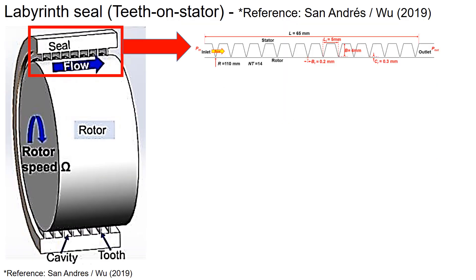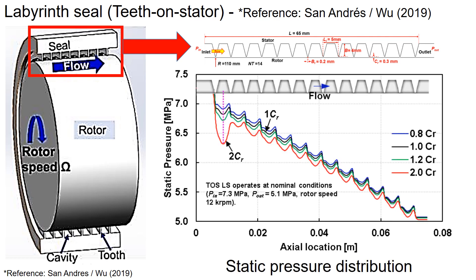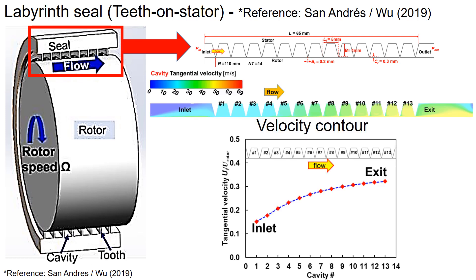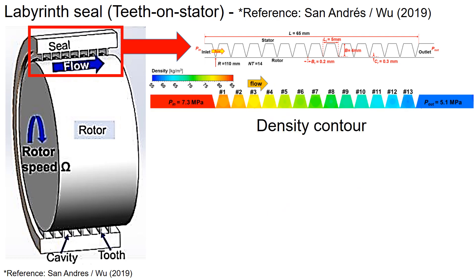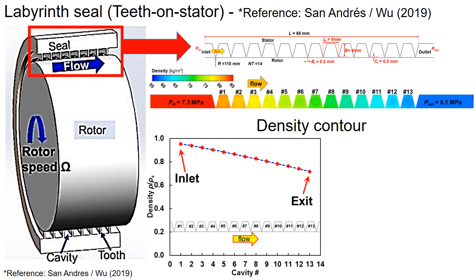Let's take a look at an example of a teeth-on-stator configuration. In this plot, we observe a decrease in static pressure along the seals towards the outlet, while the velocity tends to increase towards the seal exit. We can also see the density distribution through the cavity, with the density decreasing towards the exit.